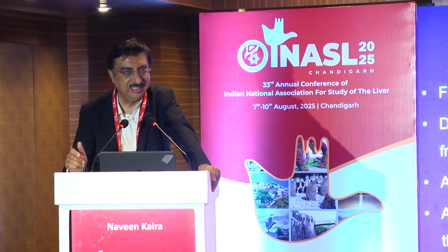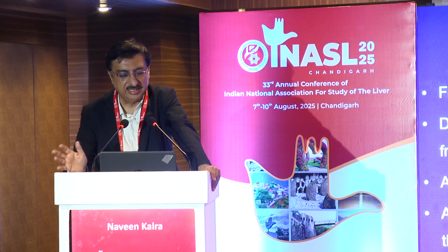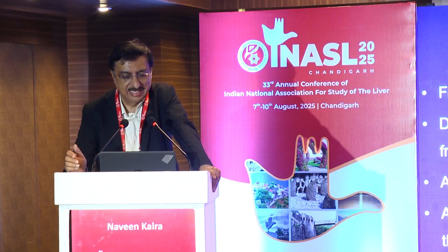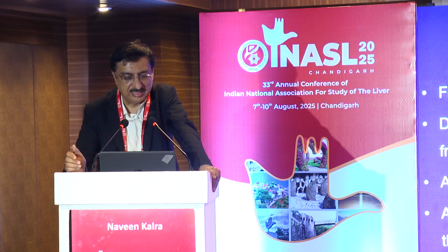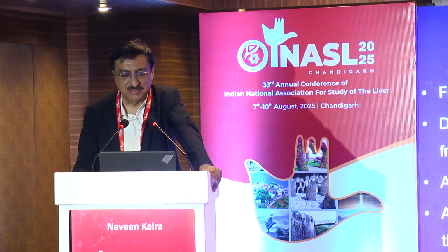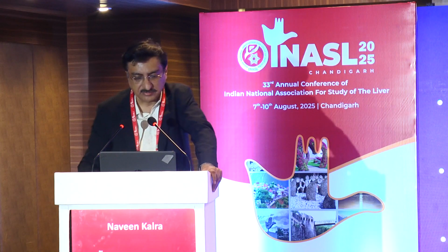If the patient is thin, you bring it down. It can also be varied according to the BMI values. But remember that low amplitude may result in low quality elastograms, while the high amplitude may make the patient uncomfortable because of the increased vibrations.